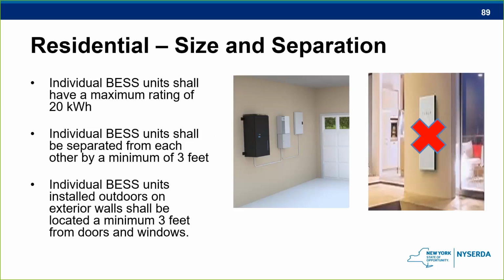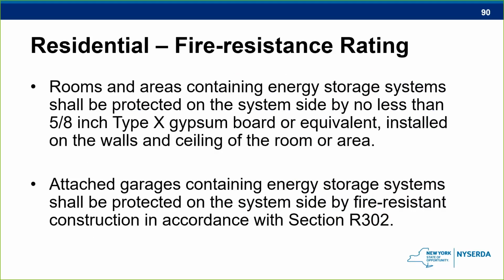And in the pictures here, notice the installations on the walls. The one that has an X through it is wrong because you cannot install an energy storage system in living spaces, if you recall from earlier. And of course, on the residential side, we also have fire rating requirements for walls and ceilings of rooms containing these systems. That's to ensure that if there is an incident, the walls can resist spreading the fire.